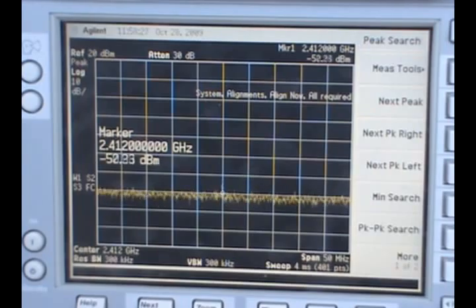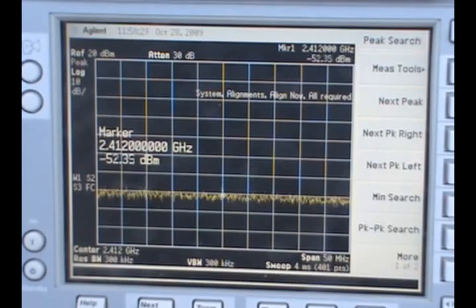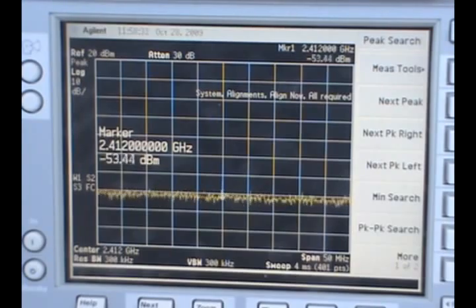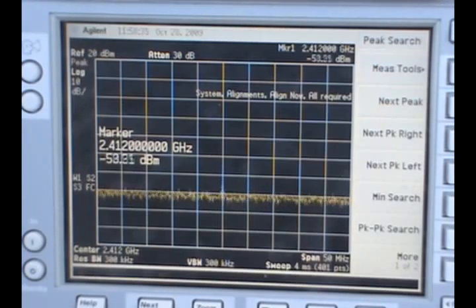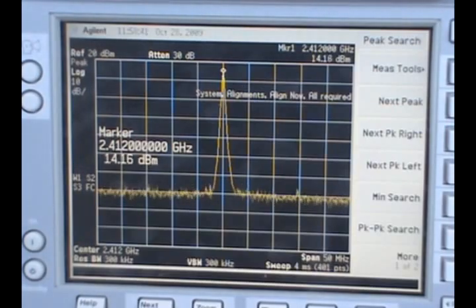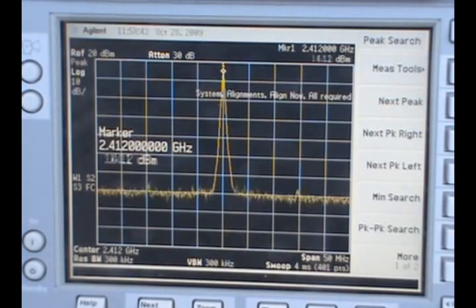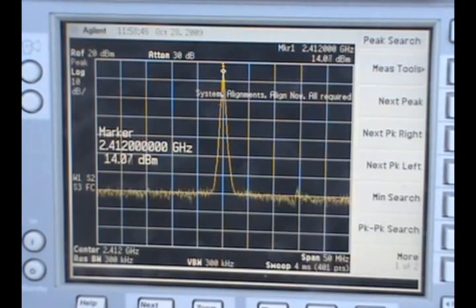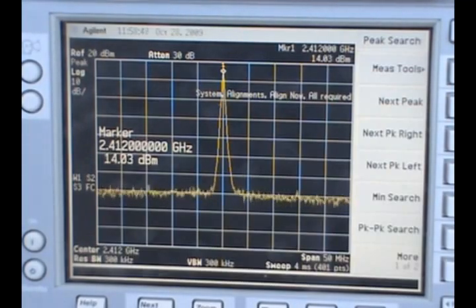Next is command 18 which generates a pure, just the carrier. It does not generate any modulated waveforms, just the carrier. This is used typically in compliance measurements to measure the power that is being transmitted. You need to use an RF power meter for this purpose.